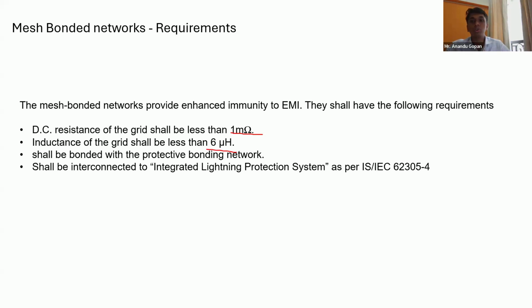You are supposed to test the continuity after an installation. And then they should be bonded with the protective bonding network. When you implement a mesh bonding network, these will be connected to your structural steel. So there is a risk of lightning effects, lightning damages.